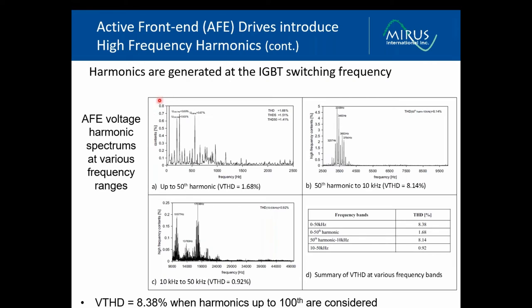If we look at percent THD and current here, very low levels. Total harmonic distortion was only 1.68%, so well within any of the requirements of marine certifying bodies, IEEE 519, or any of the IEC standards as well.